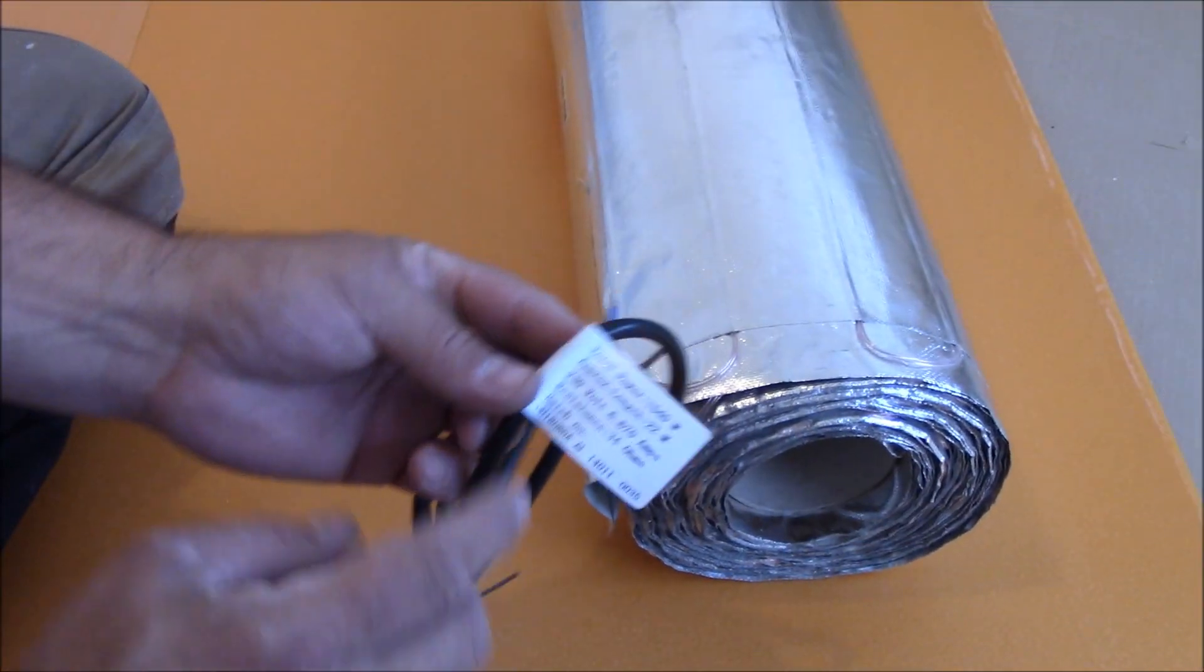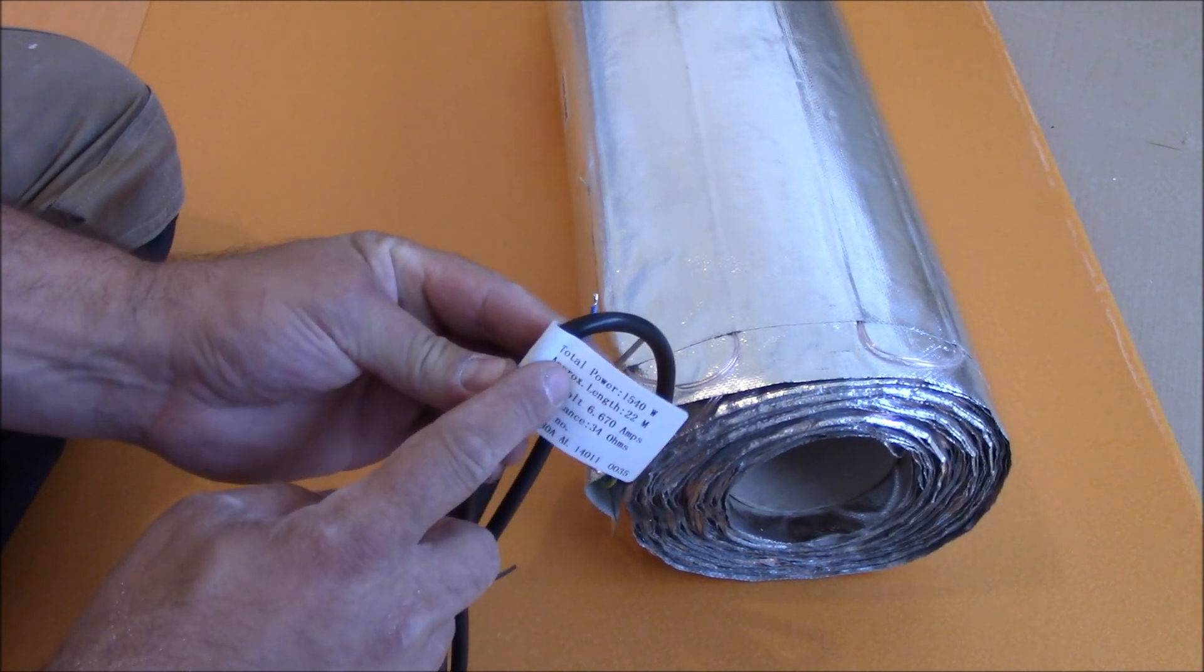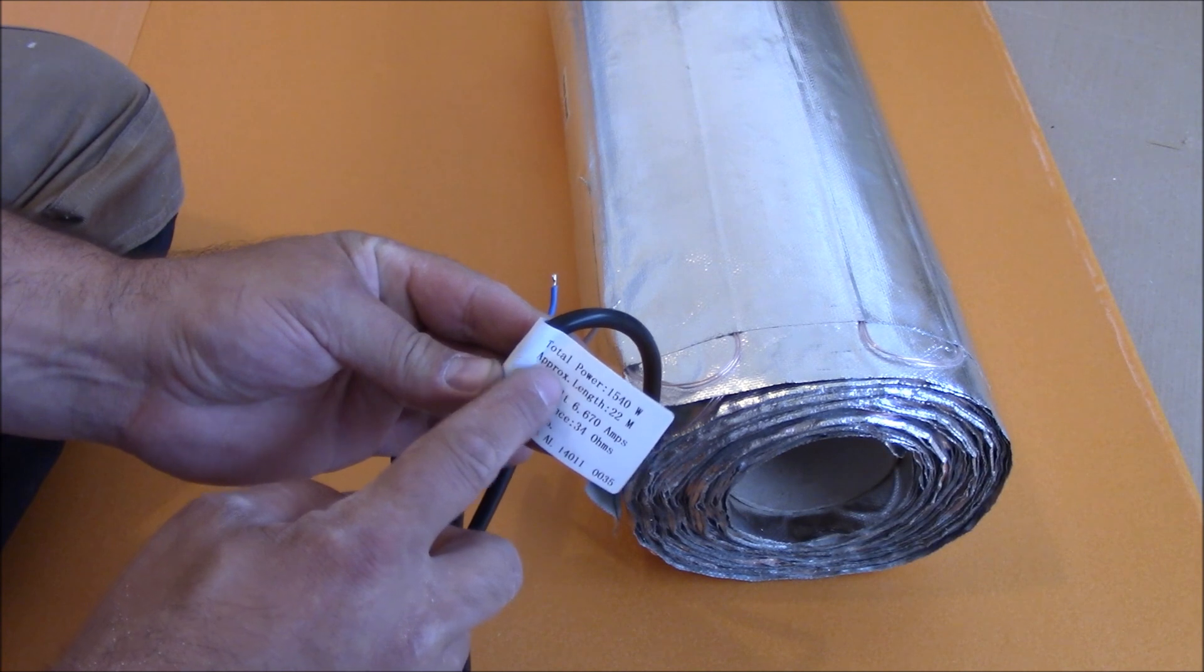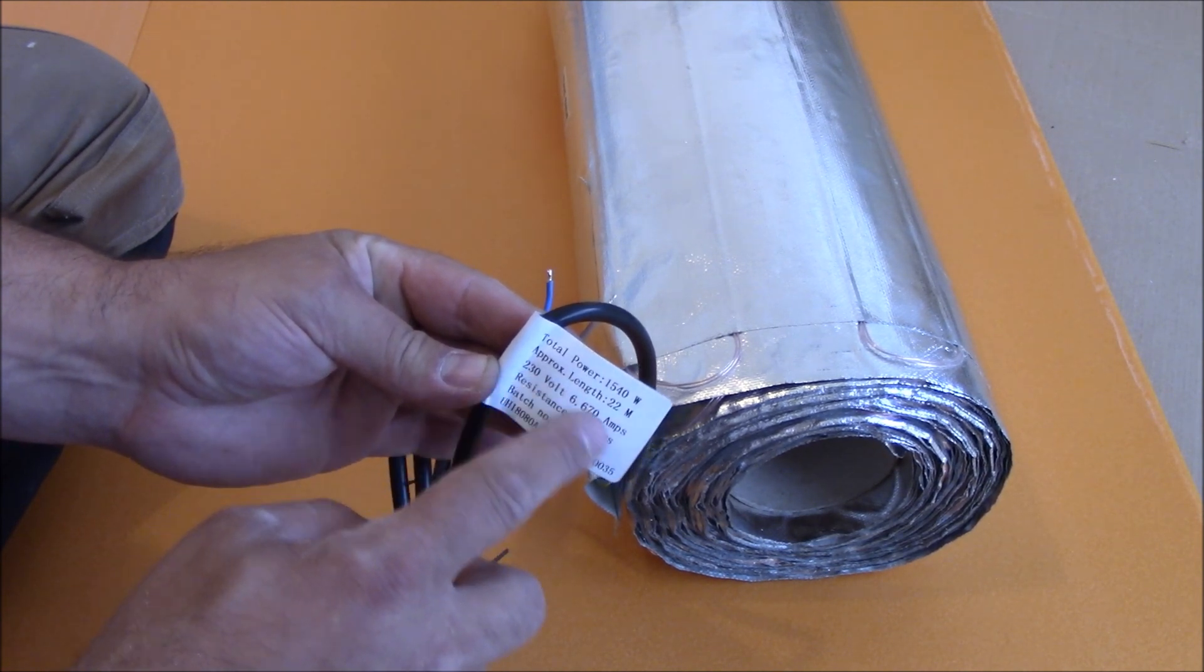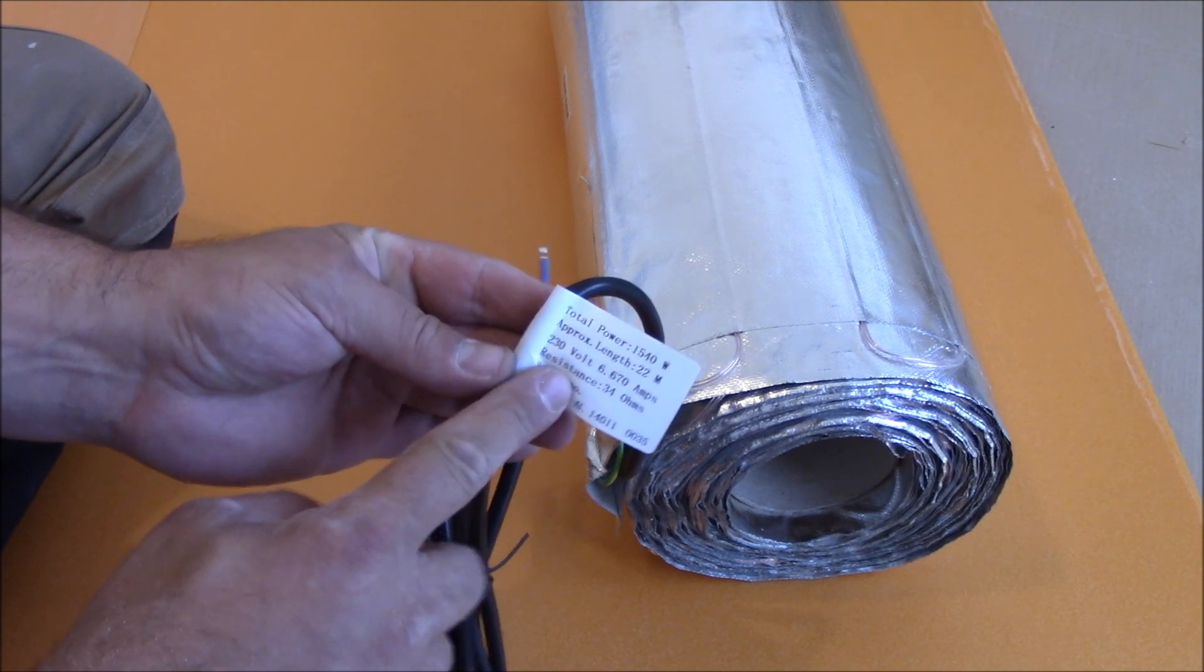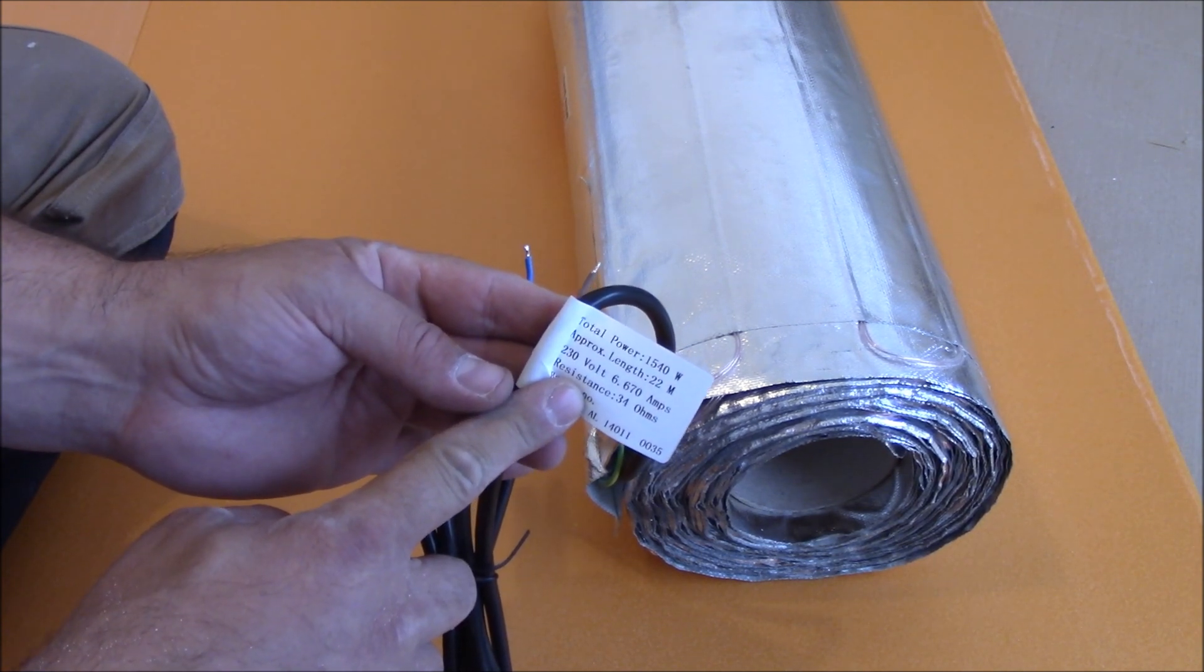On every mat there is a sticker, a label that shows some information about the mat, like the total power, the length of the mat, the voltage and the resistance in ohms. So the resistance is what we need to check.